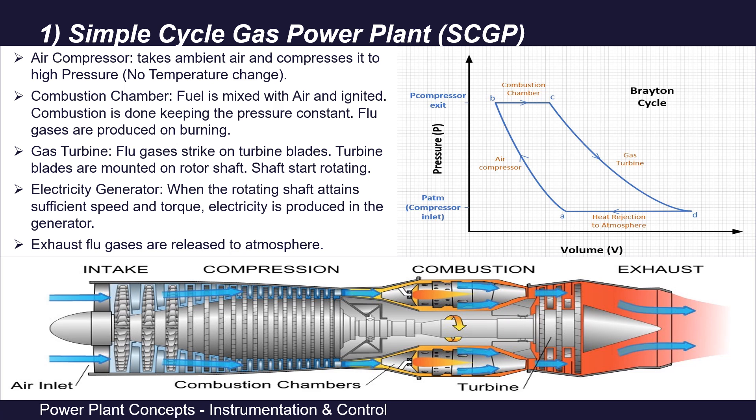Next, these flue gases are passed through the turbine blades, which are mounted on a rotor shaft. As the flue gases strike the turbine blades, the shaft starts rotating. These blades are in multiple stages to utilize the optimum energy of flue gases and to rotate the shaft with sufficient speed and torque to generate electricity in the generator. As the flue gases pass through the blades, the gases expand, thereby increasing the volume while their temperature decreases, as traced from point C to point D on the PV graph.